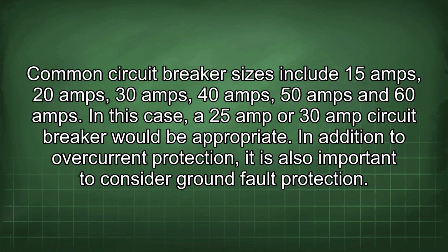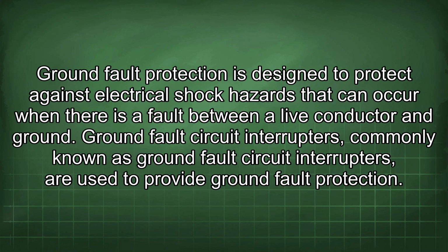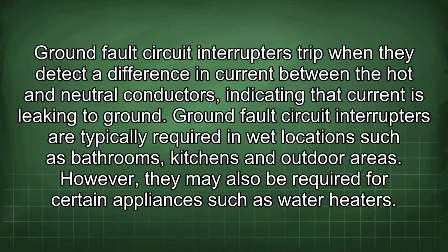In addition to overcurrent protection, it is also important to consider ground fault protection. Ground fault protection is designed to protect against electrical shock hazards that can occur when there is a fault between a live conductor and ground. Ground fault circuit interrupters are used to provide ground fault protection. Ground fault circuit interrupters trip when they detect a difference in current between the hot and neutral conductors, indicating that current is leaking to ground.